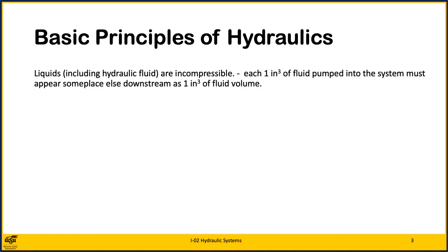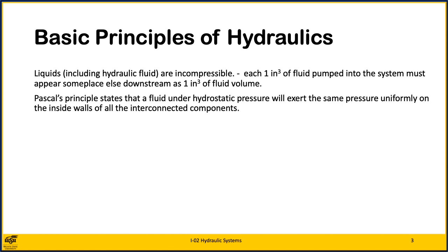Liquids, including hydraulic fluid, are incompressible, which means you can't compress them. Each 1 cubic inch of fluid pumped into the system must appear somewhere else down the stream as 1 cubic inch of fluid volume. Pascal's principle states that a fluid under hydrostatic pressure will exert the same pressure uniformly on the inside walls of all the interconnected components.